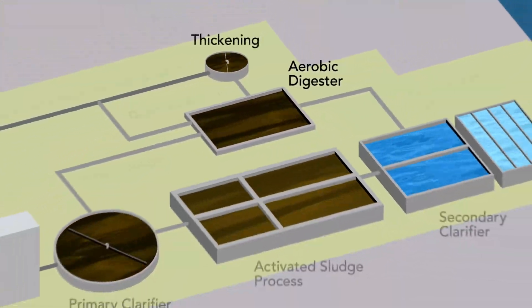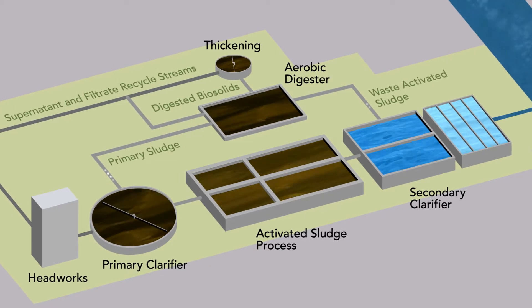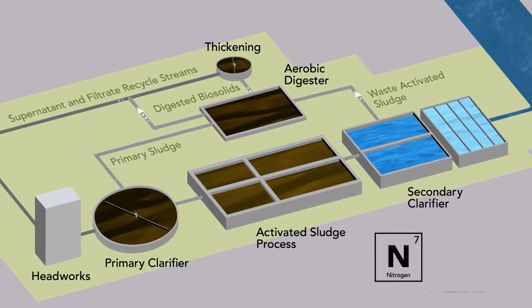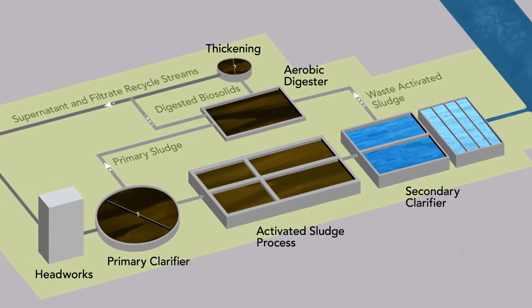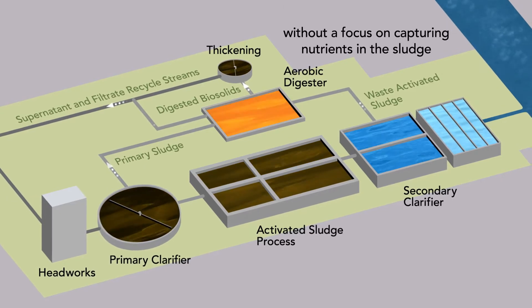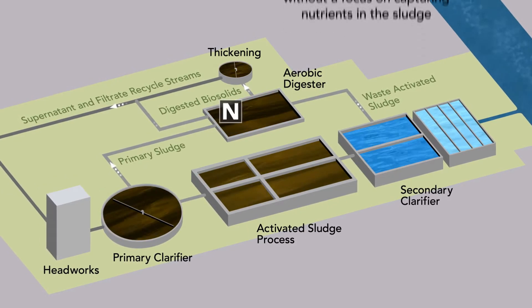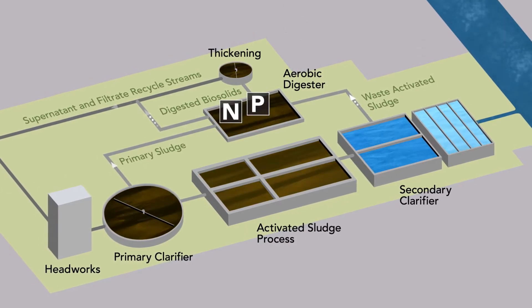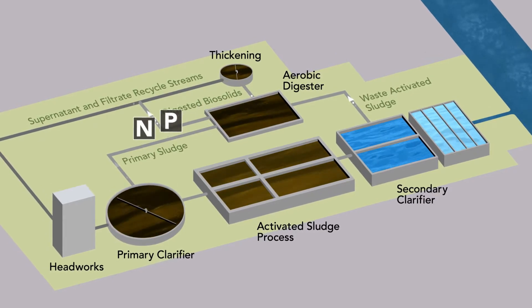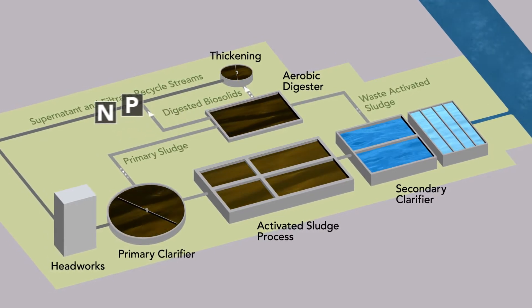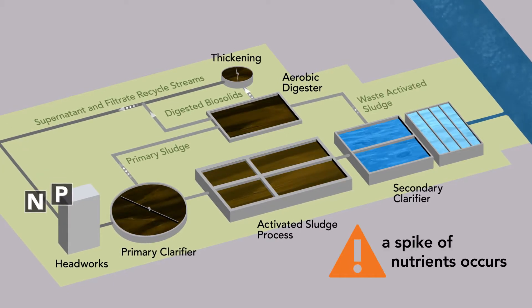Aerobic digesters are designed to break down waste sludge. During this process, nitrogen and phosphorus are solubilized. When a digester is operated without a focus on capturing nutrients in the sludge, nitrogen and phosphorus remain dissolved in the liquid. When the liquid is recycled during decanting, thickening and dewatering, a spike of nutrients occurs.